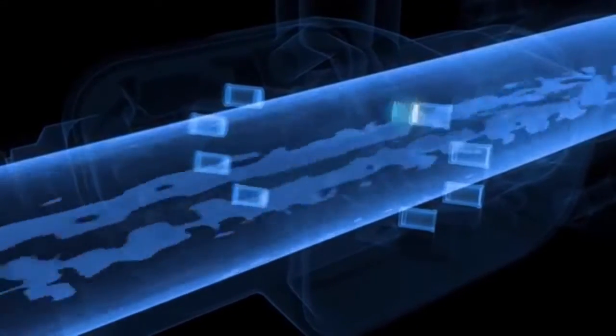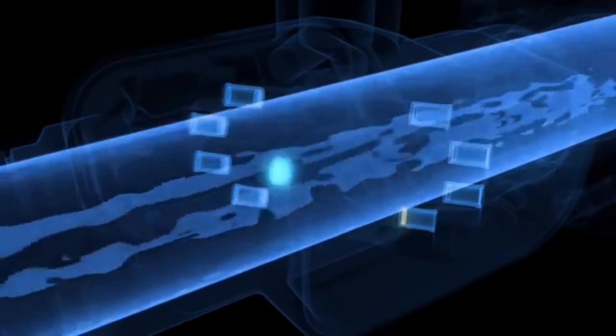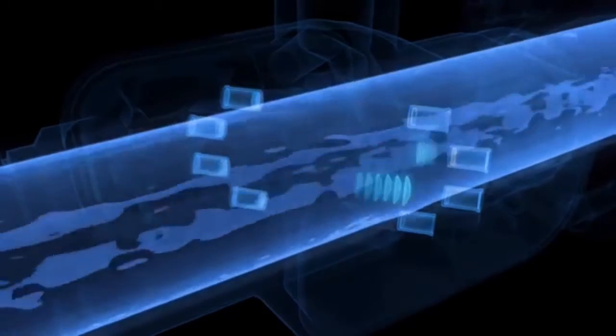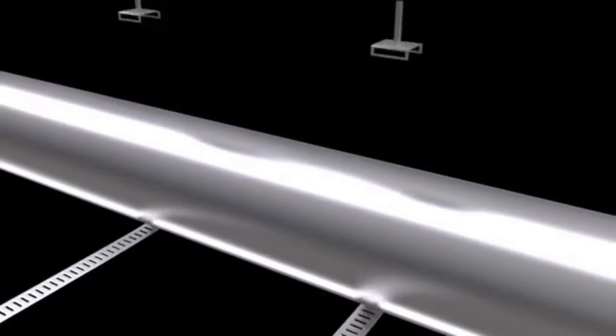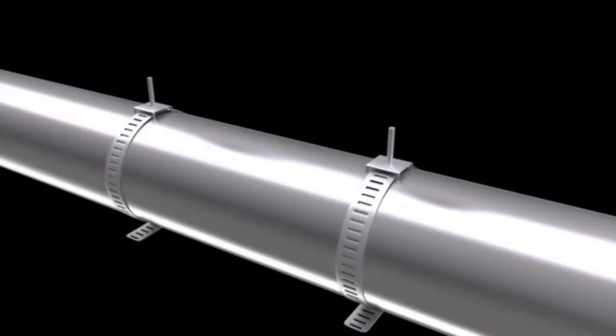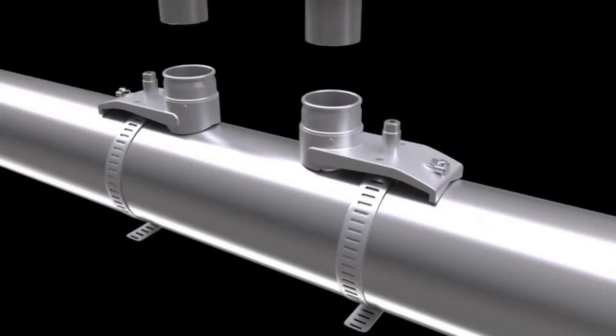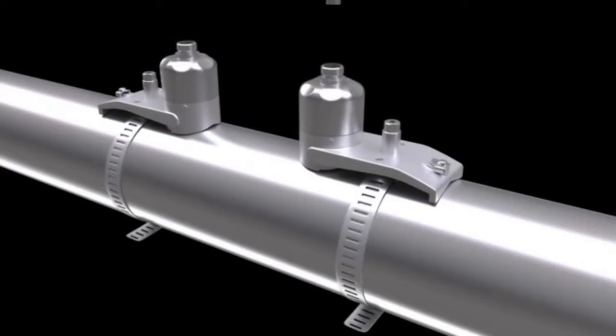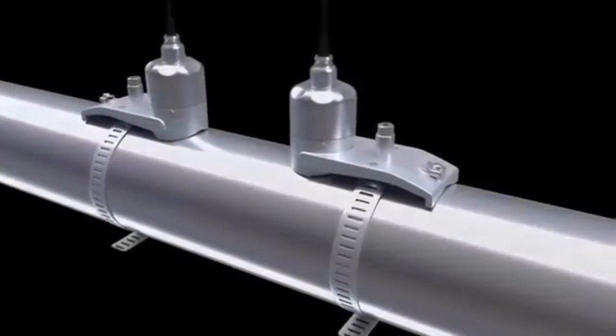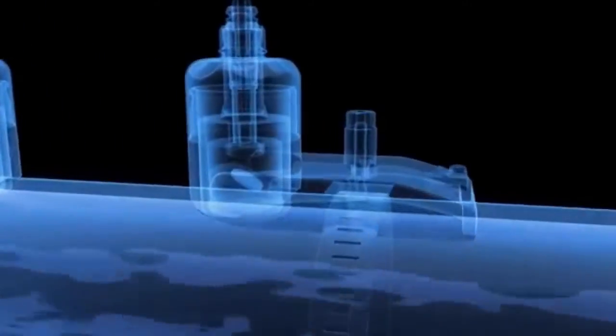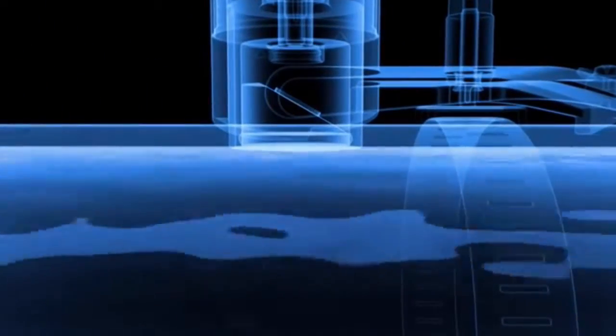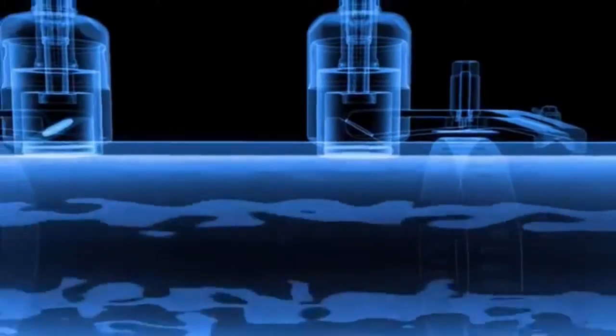For ultrasonic flow measurement, the sensors do not have to be mounted into the pipe. With a clamp-on system, the sensors are attached to the outside of the pipe. With clamp-on sensors, the ultrasonic signal is passed through the pipe wall and into the fluid, reflected on the opposite pipe wall, and measured by the second sensor. The clamp-on design allows for pipes of up to 4 meters to be measured.